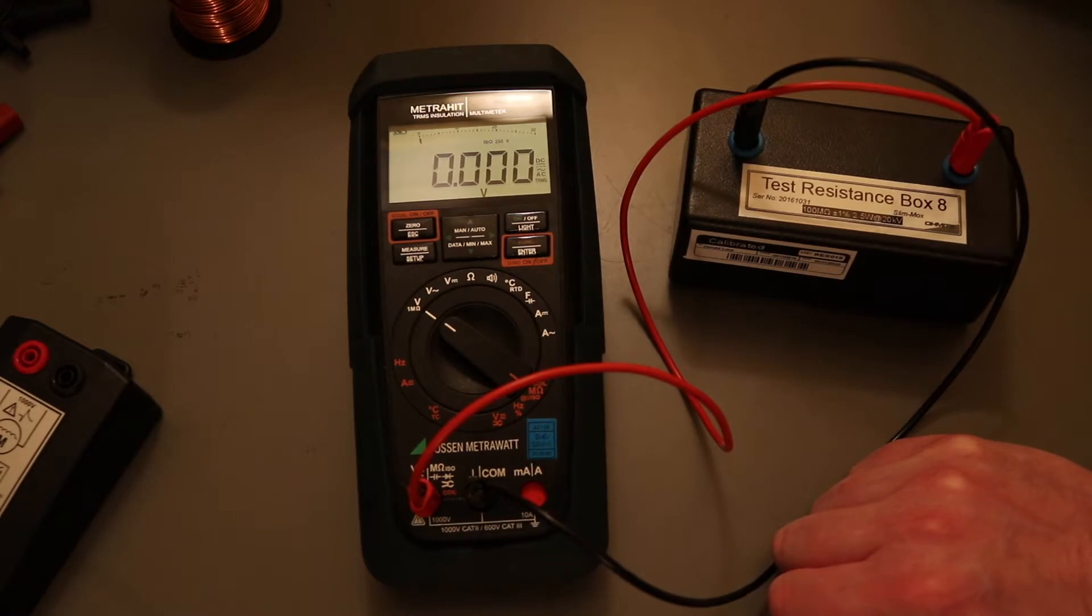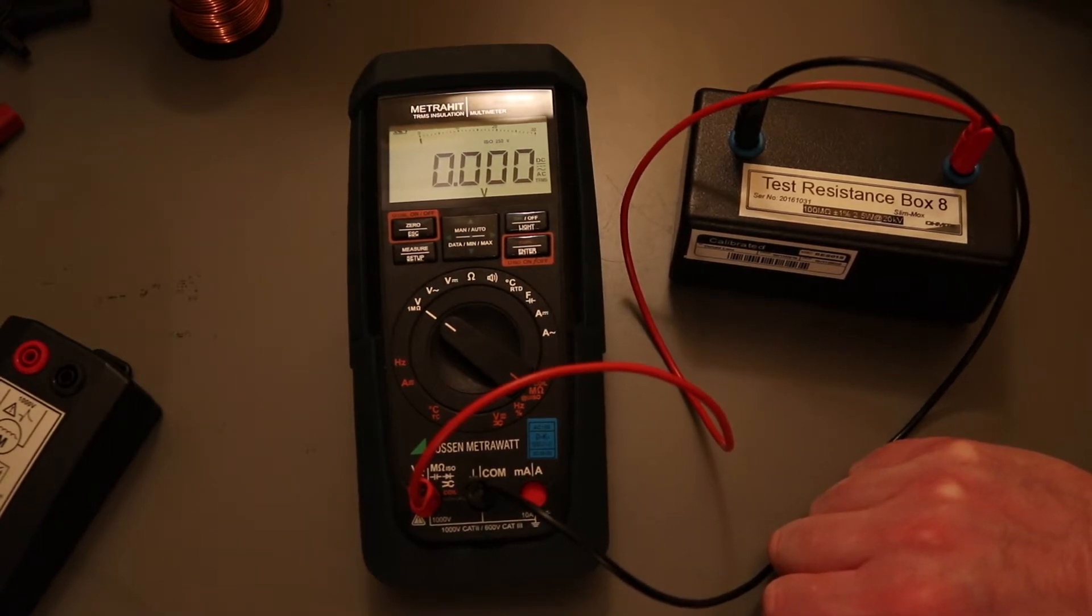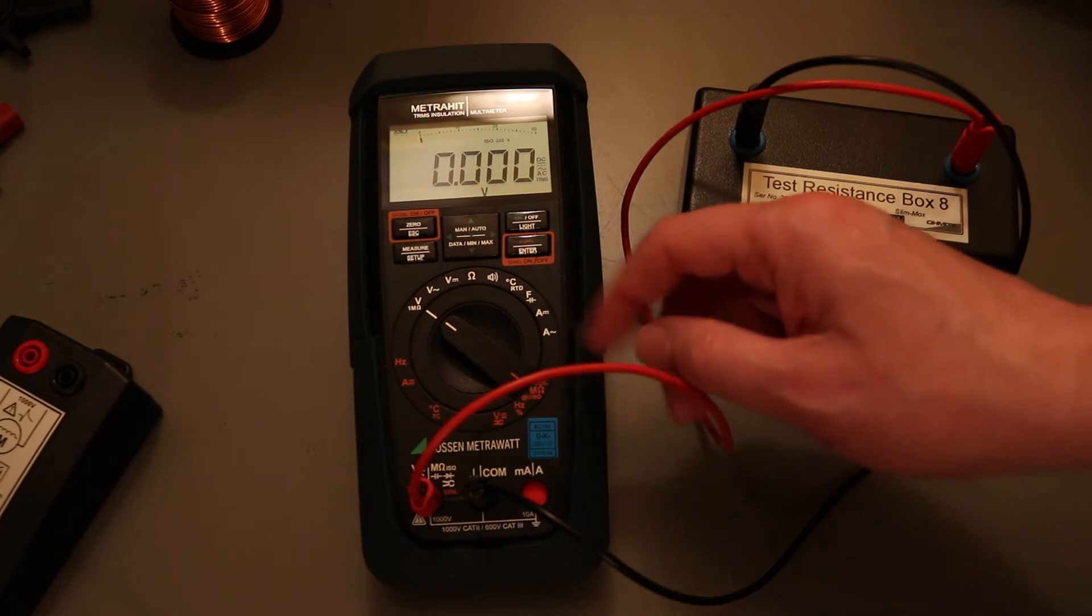All the insulation testing that I do especially on motors is one minute to the IEC standard. Well you can do it with this but it's a pain to do it.